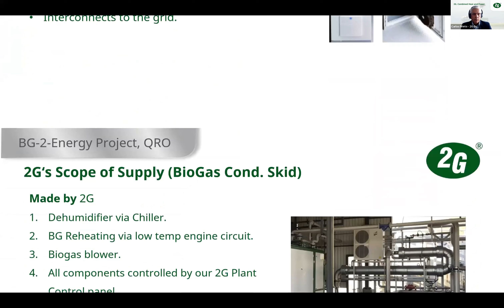Regarding the biogas conditioning skid, we supply 3 stages in this case, even though we can supply a 4 stage conditioning skid. Here the customer decided to supply the carbon activated filters themselves, but we supplied the dehumidifier system via chiller, shown here in the picture, and the biogas reheating system, which is this heat exchanger fed by the low temperature circuit coming out of the engine.